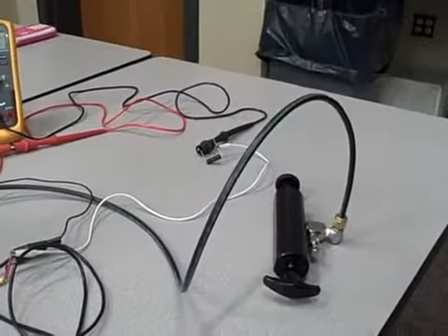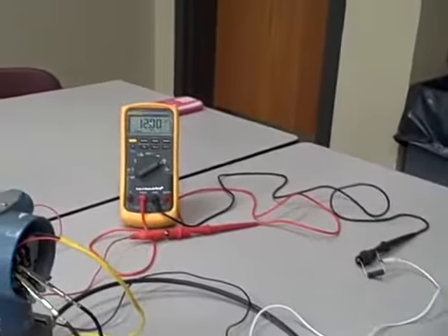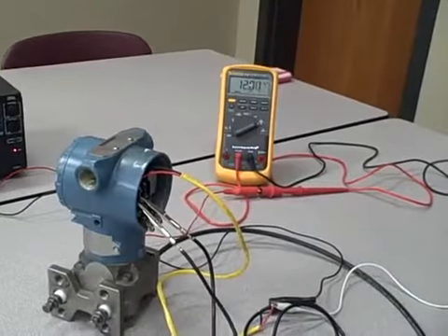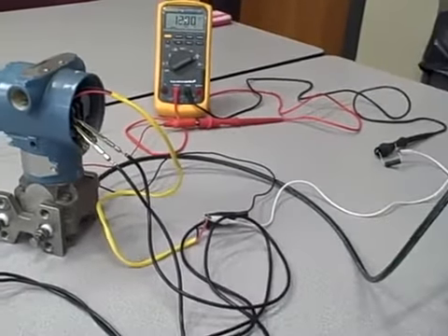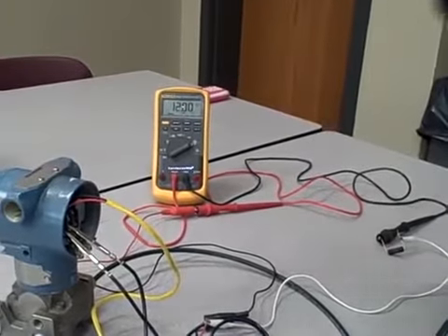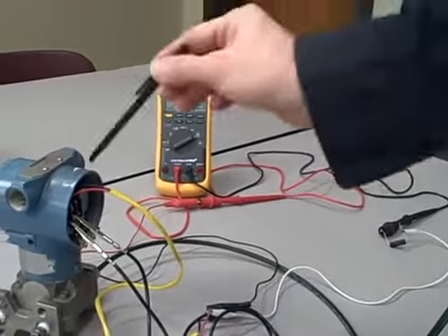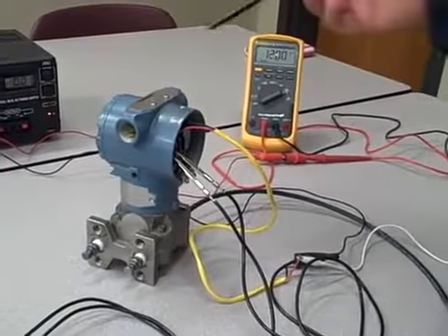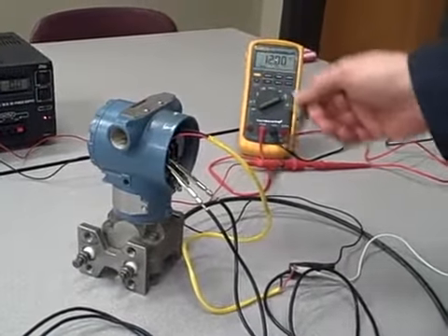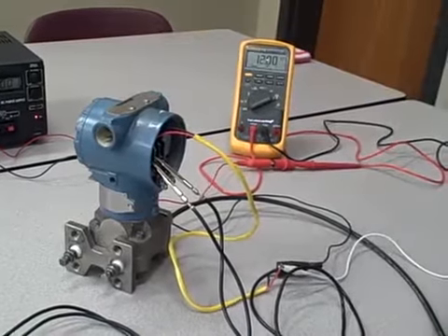It's an air pump. The range of the transmitter is 0 to 1,000 inches of water column pressure. We are applying about 500 inches of water column, which is exactly halfway in its range. That's why we see 12 milliamps out of a 4 to 20 milliamp range. This is a smart transmitter, which means it understands the HART communication protocol, little pulses of AC voltage that we superimpose in the same two wires with a DC signal.